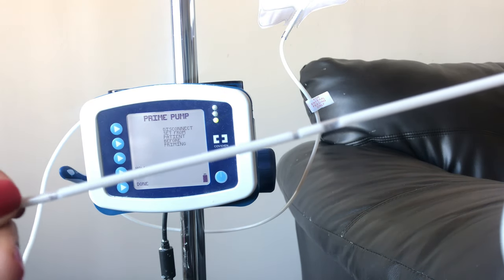A yellow light lights up when you press hold during a feed. You'll be given the options to clear the volume, adjust the settings if you want to change the feed rate, resume in minutes, and check history — this shows how much you have fed your child so far. When you're ready to exit, press done. After 10 minutes of holding, an alarm will sound showing a hold error. It will give you the option to either continue or shut down. Let's power it down.